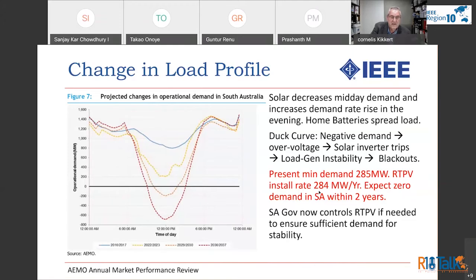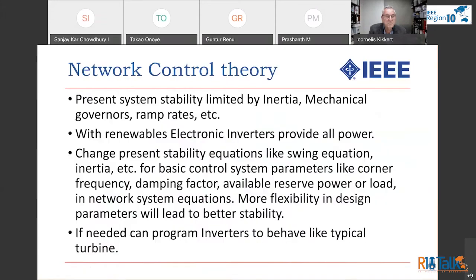In South Australia, the minimum load at the moment is 285 megawatt. The rooftop installations are about the same per year, so we expect zero demand in South Australia within 2 years. And we're probably one of the first countries or places in the world where that will happen. The South Australian government now has the ability to control rooftop PV if needed in order to ensure sufficient stability.